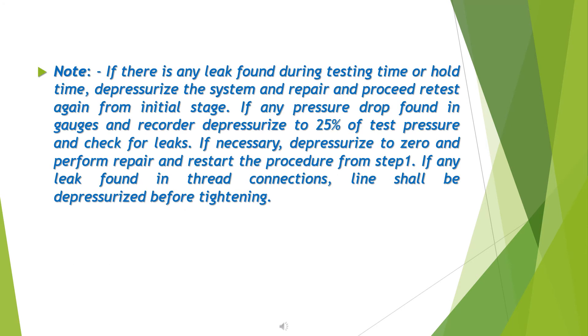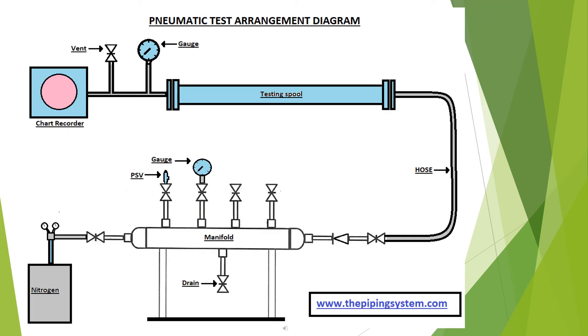Note: if any leak is found during testing or hold time, depressurize and repair, then proceed to retest from the initial stage. If a pressure drop is found in gauges and recorder, depressurize to 25% of test pressure and check for leaks. If necessary, depressurize to 0 and perform repair, then restart the procedure from Step 1. If any leak is found in threaded connections, the line shall be depressurized before tightening. A pneumatic test arrangement diagram is provided for reference.